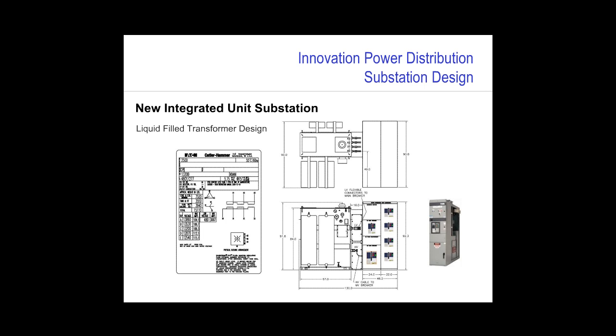Now you might be asking yourself right now, who would manufacture a transformer with both the line and load spades on the same side? Well, the answer is at least two manufacturers that I know of. And here we've shown a drawing of a typical, actually liquid-filled substation transformer with the primary spades on the lower right-hand portion of the assembly and the secondary spades on the upper right-hand portion of the assembly. We insert the integrated unit substation onto the side, and as you can see, we have 15 kV coming into this assembly and 480 volts coming out, ultimately feeding, in this case, 4 feeder circuit breakers.